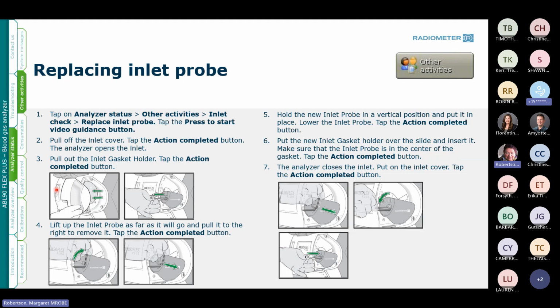Okay, and then the next step, which I don't have a video on, but there is a video on the analyzer to walk you through the process, is replacing the inlet probe. So I've just put the slide in there, which goes through the directions. And again, as I said, we'll go through that on training. It's the same method, and all we're doing is getting into the same area. We're taking off the inlet gasket, and then we're taking the probe, and you'll flip the probe up, turn to the right, and then you can pull the probe out. Then we push the new probe back in, turn it back around, place it down, and as long as it's got some activity to move, then the probe has been replaced. And again, that's one of the things we go through on training, so I'll have everybody have a chance to practice it when I'm out there working with you.